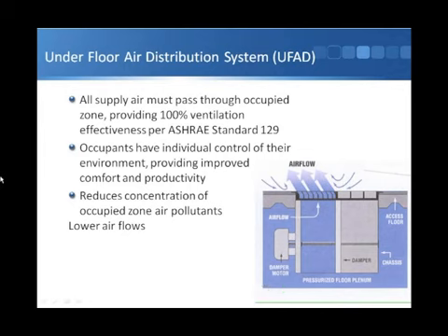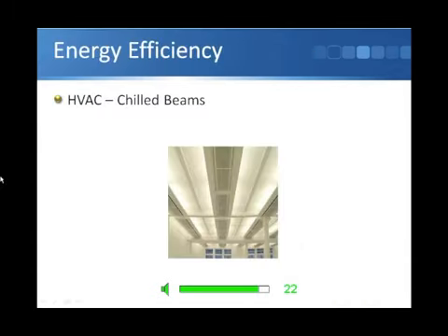So reducing the amount of air we need significantly, because the air on an underfloor air distribution system, really displacement ventilation, comes through, treats the occupied zone, and then is pulled out. There's less mixing than with those other systems.